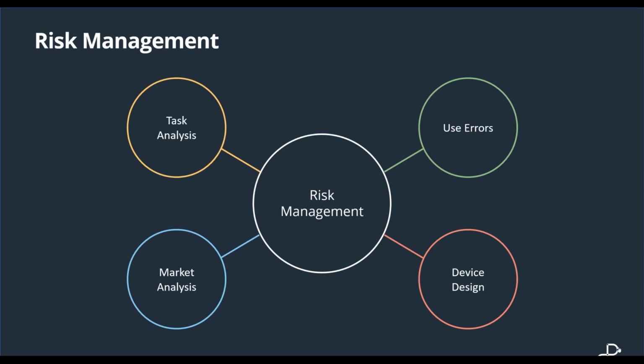Risk management, as a number of people are continually referencing at the moment with the advent of 14971:2019, is not a process where you come in at a certain point of your design inputs and chop and change, and then you leave it and come back to it. It's a life cycle process. So you should be using your user inputs right at the beginning to consider where you need to be designing for your user and your end user.